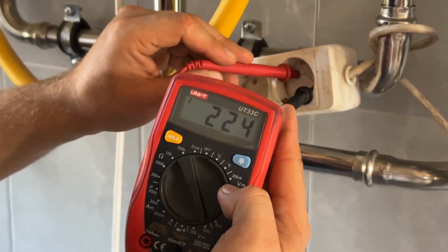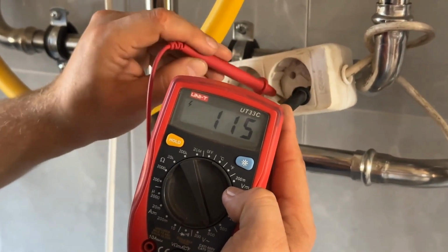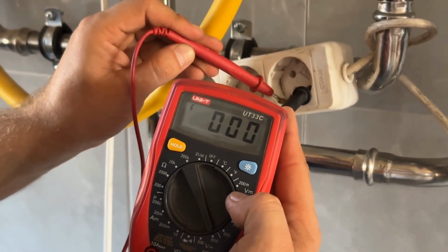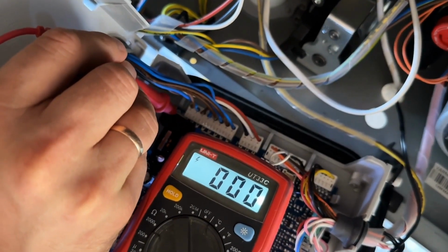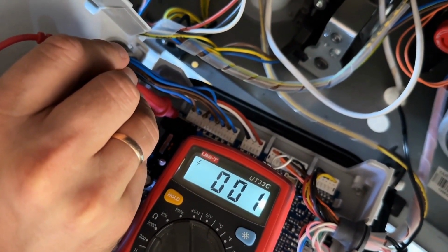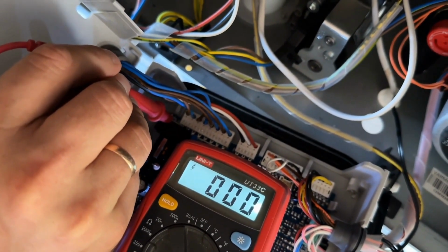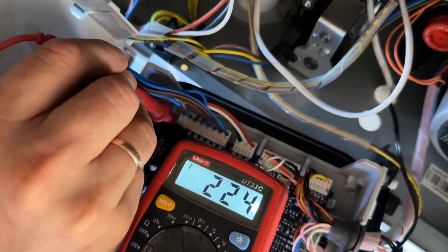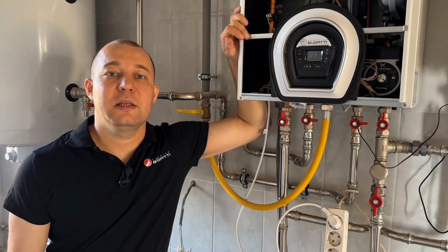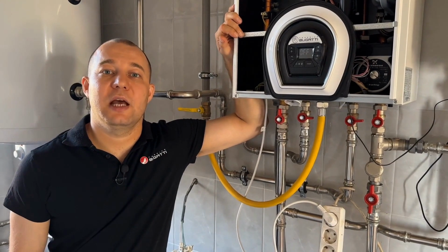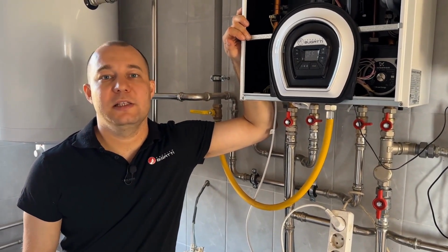We must check the voltage in the electrical network, as well as check the potential between the neutral and the ground. Although our boiler is phase independent, it is essential to check the phasing. If the phasing does not match, in our case, be sure to flip the plug. In this specific case, the voltage stabilizer is absent, but we strongly recommend its installation.